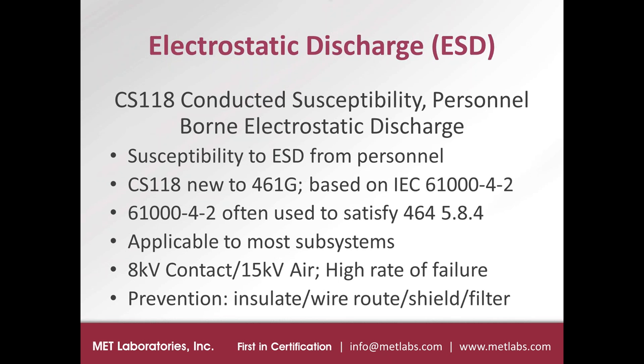Throughout the presentation, when I'm stating things called a high rate of failure, that's in my observations over testing hundreds of products in the EMC facility. These test methods have a higher rate of failure compared to the other test methods. For ESD, if you have a failure, you have a subsystem that's not compliant to the test, it malfunctions during the discharge, then modifications to design could include insulating different portions of the device, routing internal wiring differently, improving or changing the shielding of the chassis or the external or internal cables. And then also filtering of different pins and different signal lines, both internal and external, could make improvements for ESD performance.